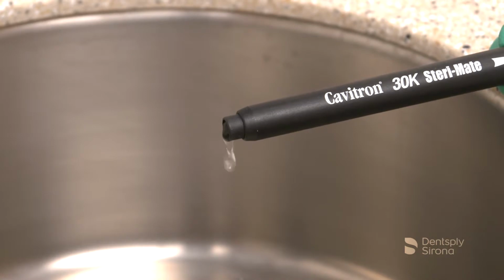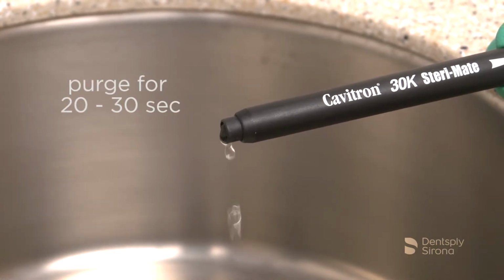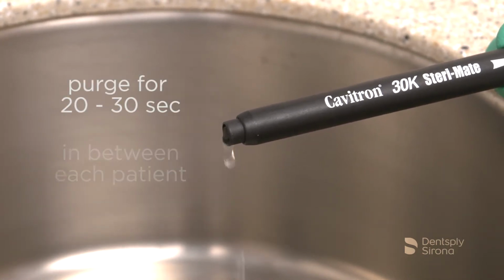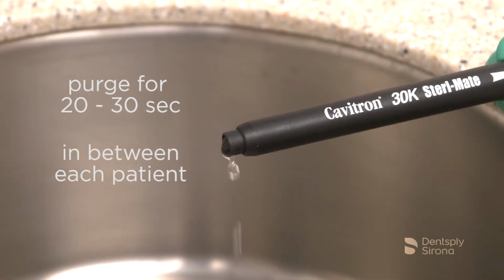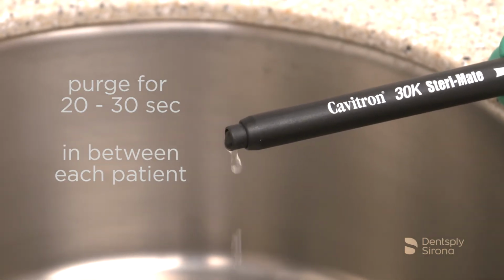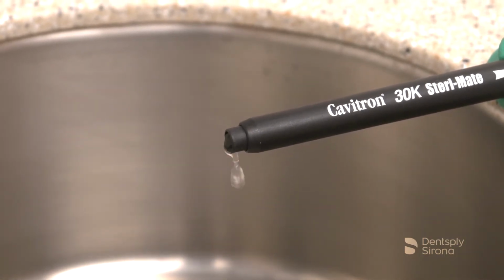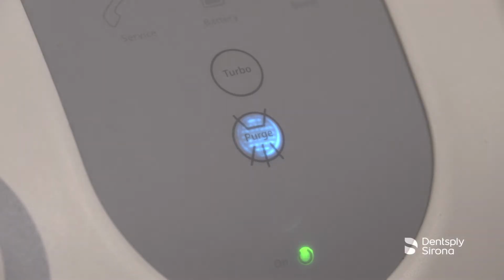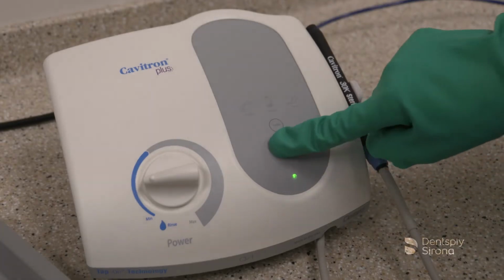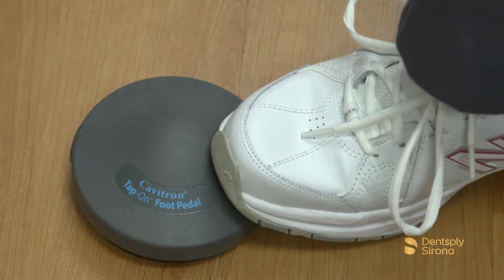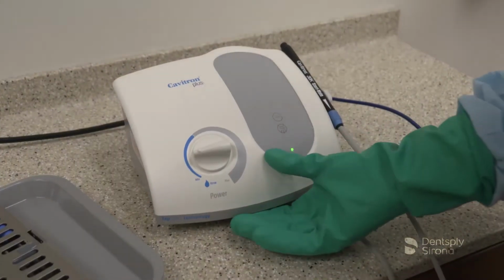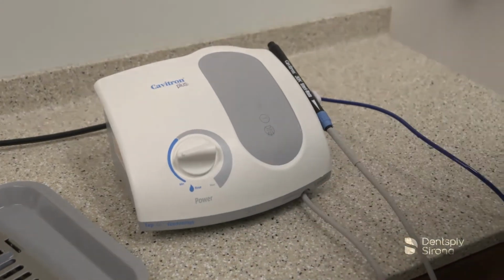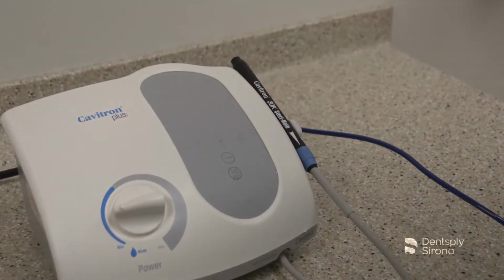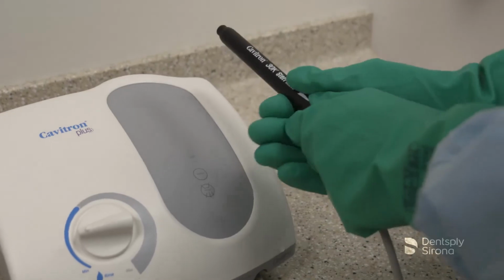Per the CDC recommended guidelines, the handpiece line should be purged for a total of 20 to 30 seconds in between each patient. This allows any patient material that may have entered the water lines to be flushed out. To interrupt the 2-minute purge cycle after 30 seconds, press the purge control button again or simply press the tap-on foot pedal. After the purge cycle is complete, turn the system to the off position. Remove the SteriMate handpiece from the unit.